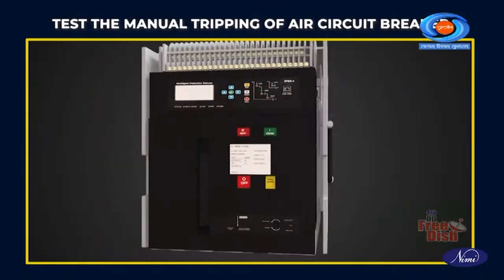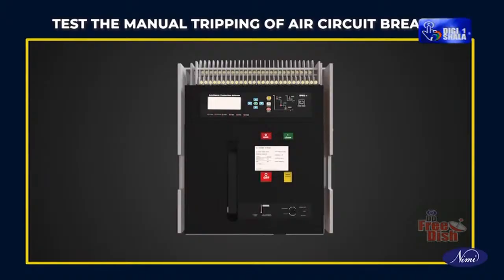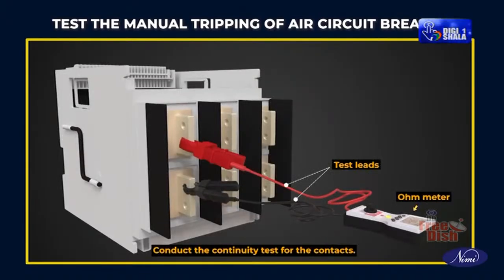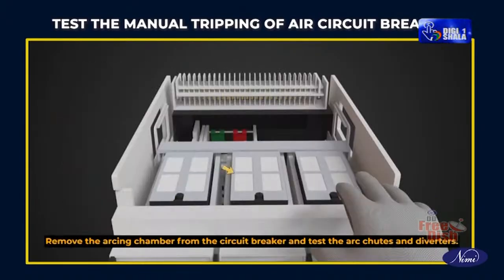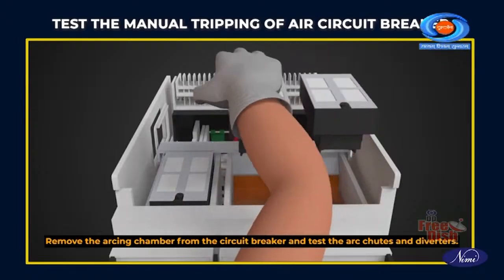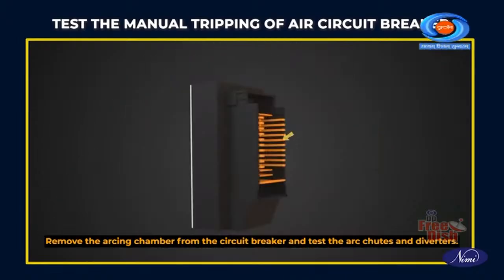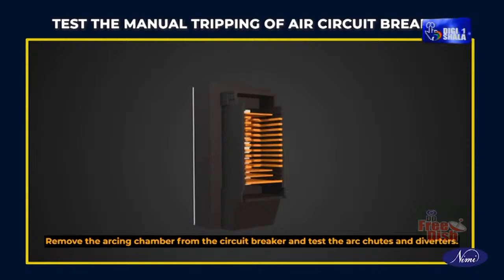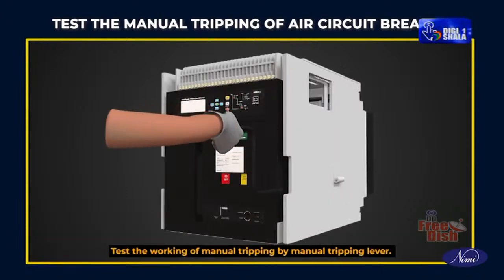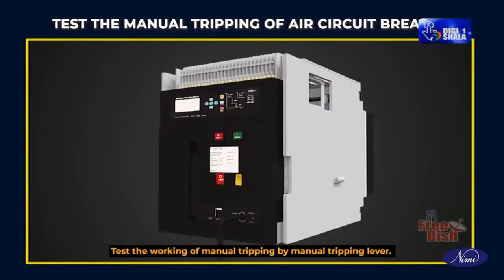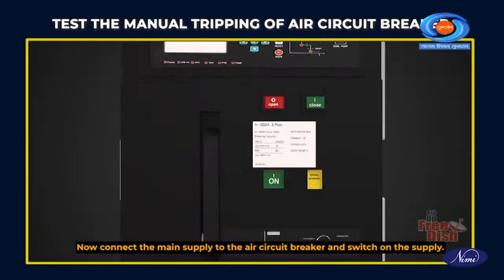Test the manual tripping of the air circuit breaker. Conduct the continuity test for the contacts. Remove the arcing chamber from the circuit breaker and test the arc chutes and diverters. Test the working of manual tripping by the manual tripping lever. Now connect the main supply to the air circuit breaker and switch on the supply.